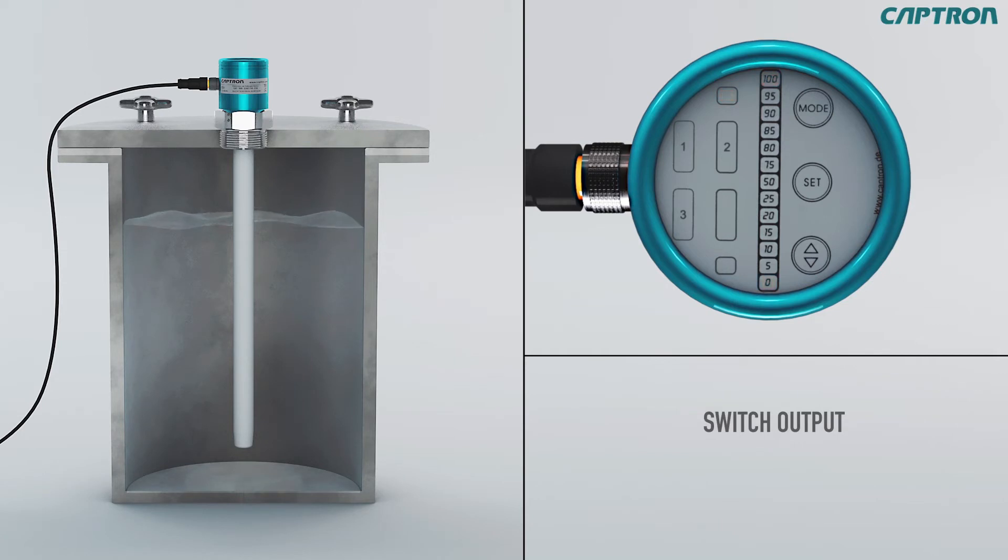Setting the switch output PNP1. The 0 and 100% displays will light up once again as well as the NO or NC display for PNP1. NO stands for normally open and NC for normally closed contact. You can set NO or NC with the up down button. Confirm your adjustment with set.